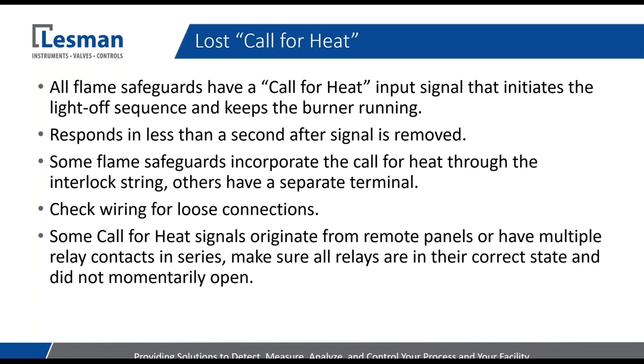Another point is that some flame safeguards have the call for heat going through the same terminal as the interlock string — your low gas, high gas, combustion air pressure interlocks — all of the ones you normally see feeding into the flame safeguard. Once all interlocks are satisfied, it goes through the light-off sequence. You should be aware of which type of flame safeguard you have and how that call for heat is being introduced into the system. Know that if you have a system that turns the burner off but doesn't cause an alarm, it's most likely coming from a loss of the call for heat signal.